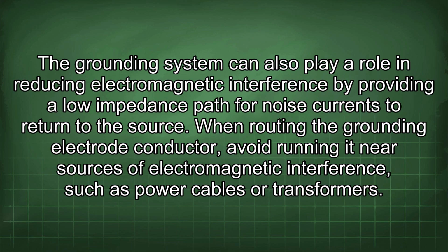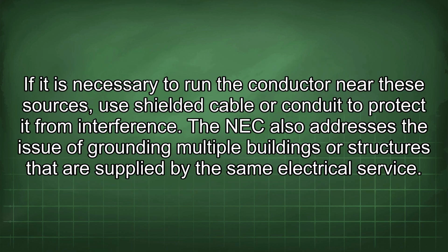When routing the grounding electrode conductor, avoid running it near sources of electromagnetic interference such as power cables or transformers. If it is necessary to run the conductor near these sources, use shielded cable or conduit to protect it from interference.